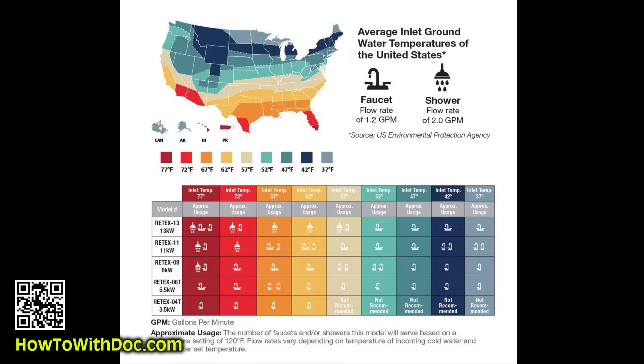The first thing you need to understand is your temperature of the incoming water does have an impact on the performance of these things. If you look at manufacturer's charts, they'll show you: if your incoming water is 40, 50, or 60 degrees, you're only going to be able to raise your water maybe 20, 25, or 30 degrees based on the flow. So it does have an impact.